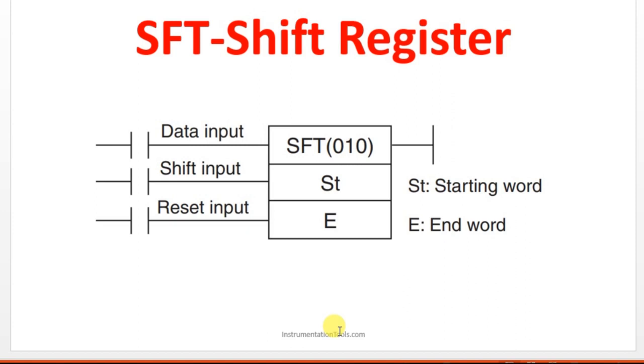SFT is the instruction for shift registers, instruction name for shift register in Omron PLC. Here we are having 5 variables. One is data input, another one is shift input, another one is reset and we have 2 word addresses which are starting word and ending word.